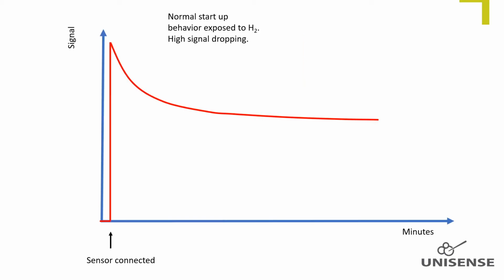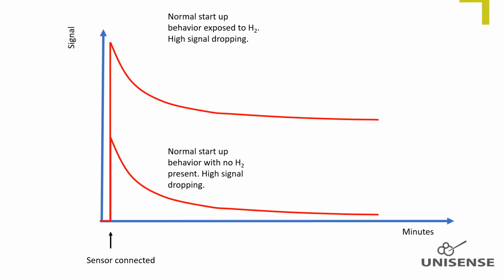These curves illustrate a normal start-up behavior of a hydrogen microsensor when connected to a Unisense amplifier and polarized. The signal is high and downward drifting right after polarization due to unspecific reactions on the working electrode. The hydrogen sensor quickly stabilizes after connecting it to the amplifier and is ready for calibration after a few minutes of polarization.